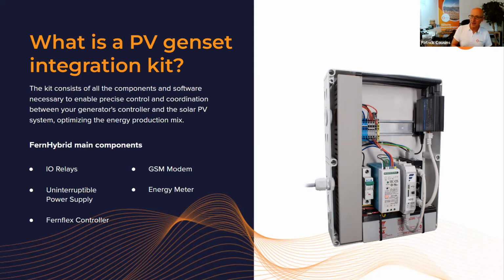What you see in the picture is a basic version of Fern Hybrid, which consists basically of the Fern Flex controller, the device on the lower right-hand side, which collects data. It needs to remain powered, so we have an uninterrupted power supply in there. We monitor that the power is available and the battery is okay. We also have an Ethernet switch, and that data then goes to Fern View via a modem.